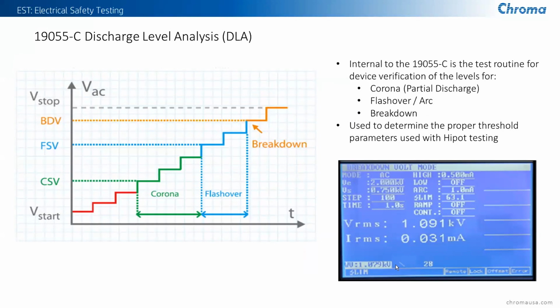Another feature of the 19055C is for you to do a discharge level analysis of your device. What you can do is program in a ramp type test at different stair-step tests to determine if your unit has potentially a corona, or a test where you start to see the lower level breakdown or leakage or partial discharge occurring. And also at the higher level, you might start to see that looking like a flashover or an arc, and then of course into total breakdown.